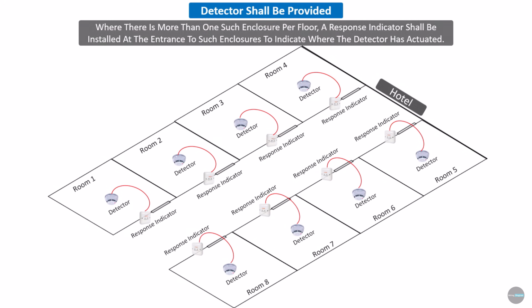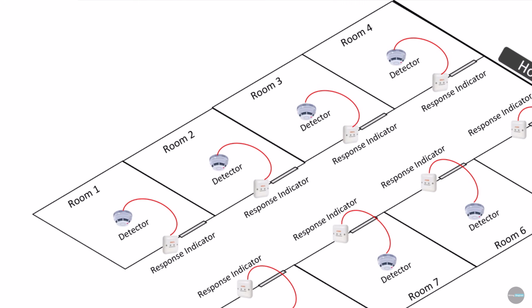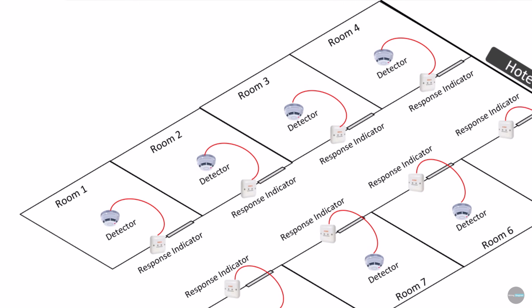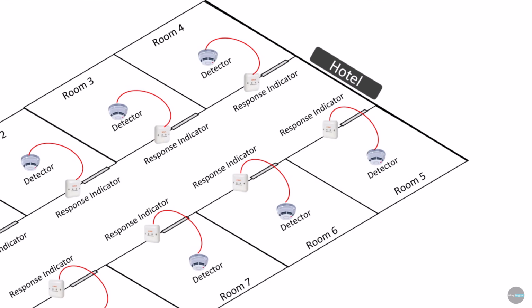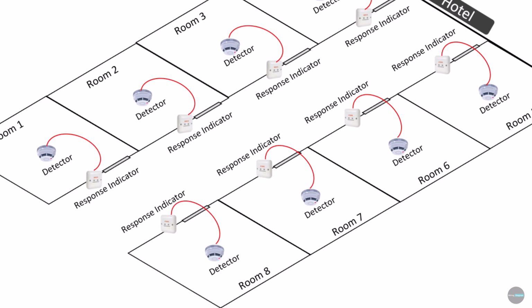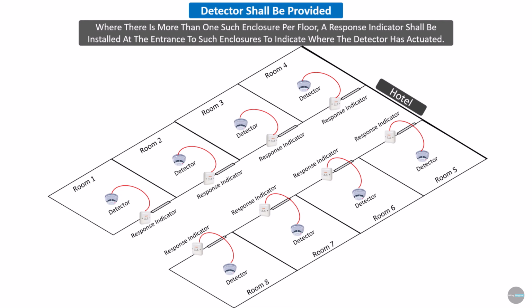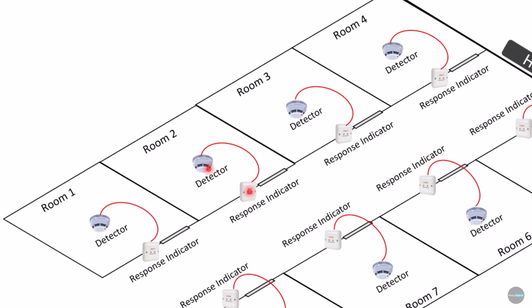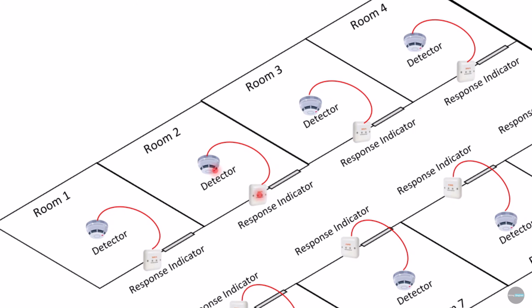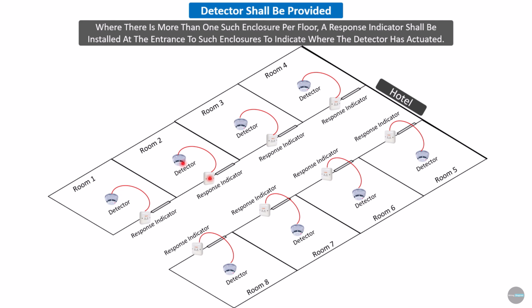In hotels, business buildings, or hospitals, where each floor has many rooms or offices, it is necessary to install a response indicator at the entrance of each room or office on the passage side. This is because when the detector inside the room or office activates, the response indicator will also activate, allowing us to identify from outside that a fire event has occurred inside that particular room or office.